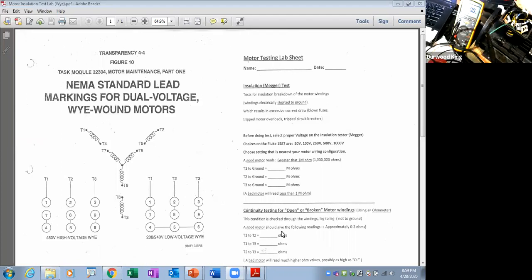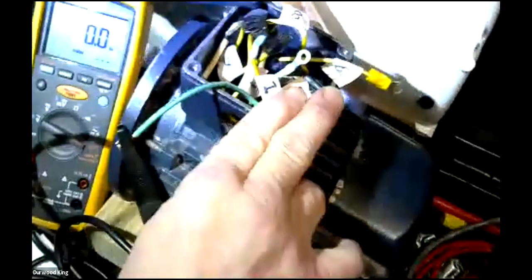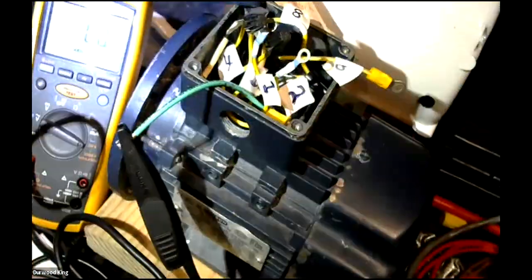And all that's telling you is, do you have a broken winding, or are the windings starting to deteriorate and get a high resistance internally? And larger motors are going to give you between 0 and 3 ohms. Smaller ones like this white one in here are going to actually be higher ohms, around 20 or 25 ohms. But they'll all be balanced readings between those 3 sets there. So when you get the 3 readings, they should be very, very similar. So let's go back to the camera, and let's check the bad motor, and we're going to go through the windings, not the ground.